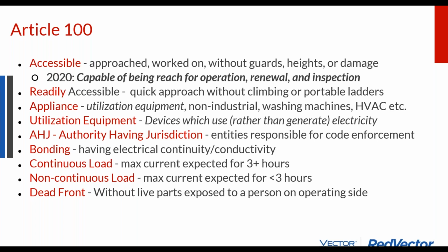AHJ is the authority having jurisdiction. So ultimately, it's your local authority, your local permit office, whether it be the power company or the distribution cooperative or the state or the city inspector. One of those entities is the one that says we are going to mandate the National Electric Code. And it is actually quite common for a local jurisdiction to not only mandate the electric code, but make additional rules or regulations pertinent to their area.